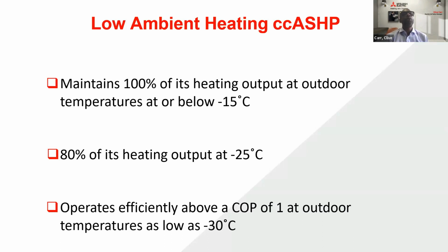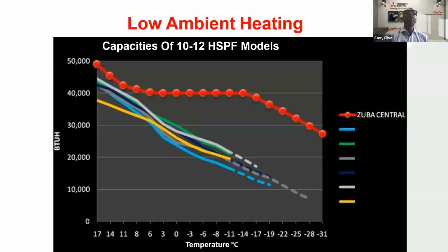We see here with our product that 80% of the heating capacity is available at the low point of minus 25. Operating efficiency is above 1 at these temperatures, and we can go right now as low as minus 30, minus 35, given the different models that you're working with. We see the graph illustrated here, where yes, at the milder temperatures, you get more heating capacity. But the reality is at the higher temperatures, 17 degrees Celsius, 14 degrees Celsius, you do not need this high capacity of heat. Where you really need the high capacity of heat is down at the lower temperatures.